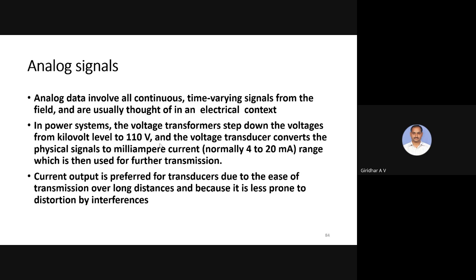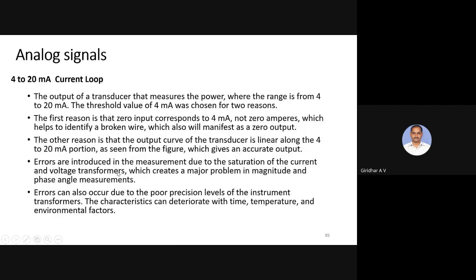In that way, it will be measured. So why are we using this, from the analog signals, voltage transformers? Even if we convert using transducers to current output, we can transmit it over a long distance without drops. In that way, it is also less prone to distortion from interference. So in those aspects, the current output will be preferred from the transducers rather than voltage.